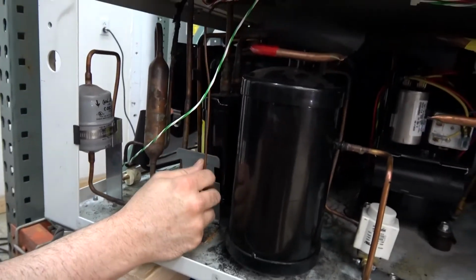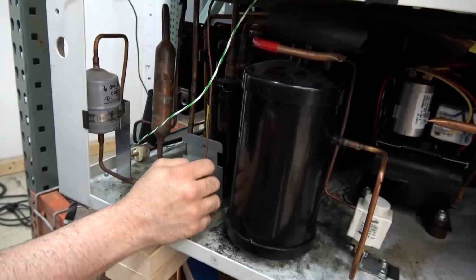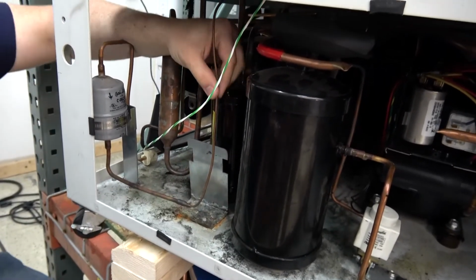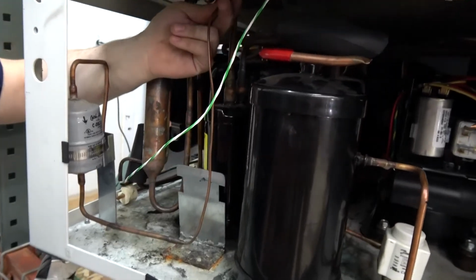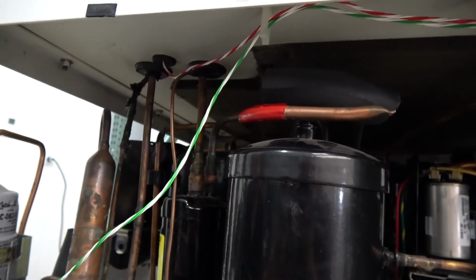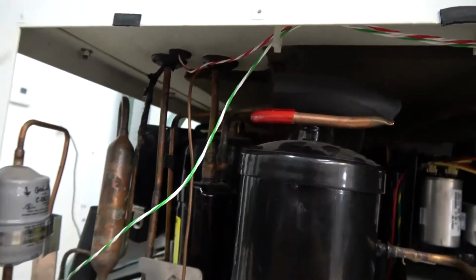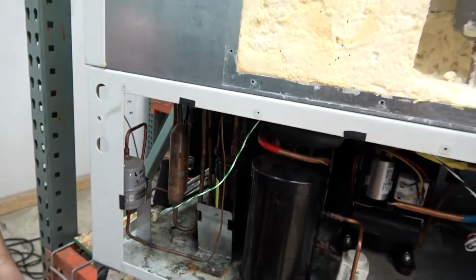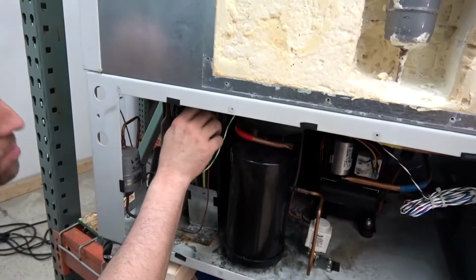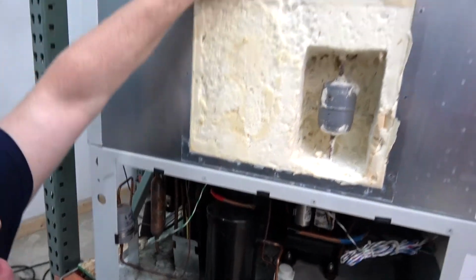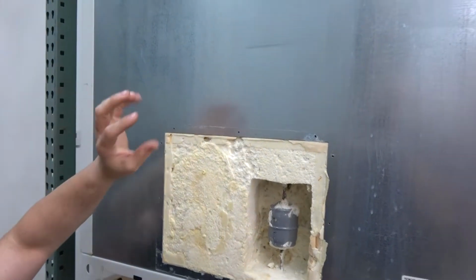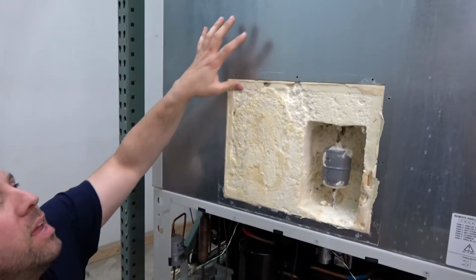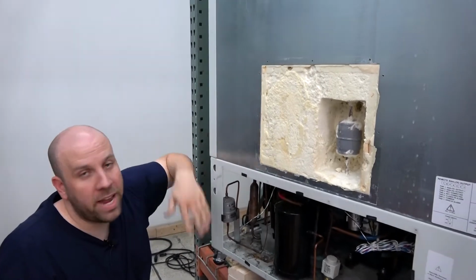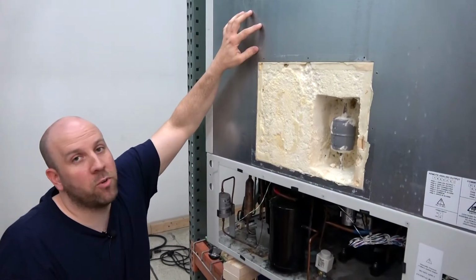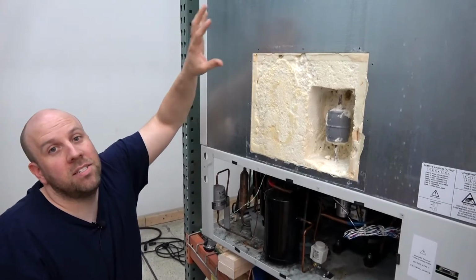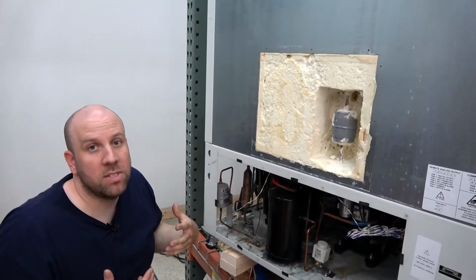I guess I should have probably mentioned this too in the component area. But this capillary tube is essentially a metering device that controls how much refrigerant flows into that heat exchanger we talked about. So it comes in here in a liquid, still under a decent amount of pressure, and it comes up through the capillary tube, up into that heat exchanger we talked about, and then it goes into a decently large volume. At that point, the pressure drops way down, and the liquid refrigerant evaporates again and sucks all the heat out of that chamber that it's in.